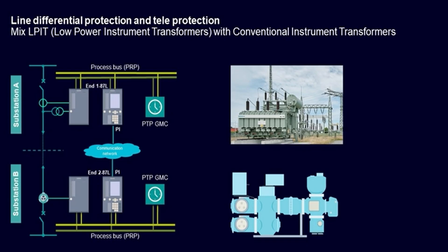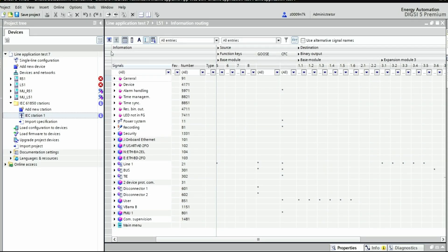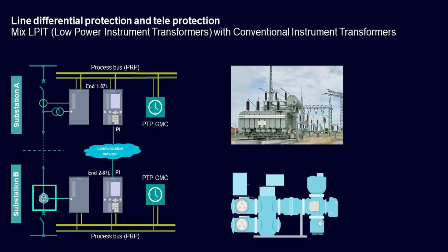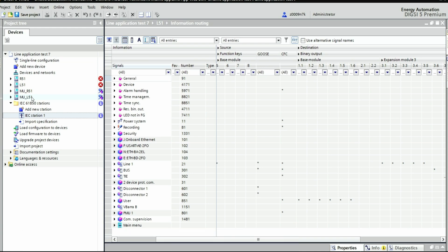Line differential protection requires sharing information between two different stations. SIPROTEC 5 7SL87 supports the use of conventional instrument transformers on one end connected to a merging unit that supports IEC 61850-9-2 sampled measurement values, and on the other end the use of low-power instrument transformers (LPIT) connected to a merging unit also supporting IEC 61850-9-2 sampled measurement values. Based on that configuration, the line differential protection 87L can be executed in a secure and stable way. We open DIGSI software to configure the SIPROTEC 5 devices and the merging unit. One merging unit has a low-power instrument transformer LPIT from Siemens Energy, and the second merging unit is connected to a conventional instrument transformer. Please refer to the first process bus video, transformer protection application with process bus.